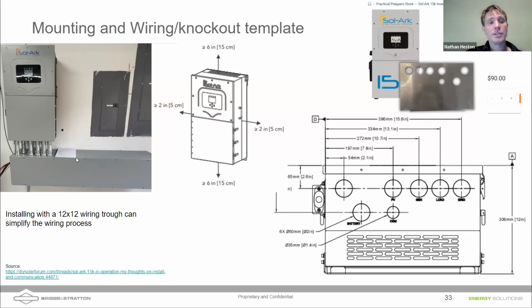It becomes much easier to install this inverter if you use a wiring trough, and I recommend getting a 12 by 12 with variable length wiring trough to help with cable management. The inverter needs 6 inches above it or more and 6 inches below it or more. So it looks like we're barely meeting that here with this example on the left.